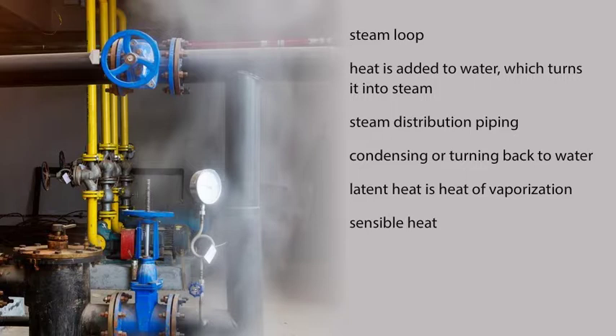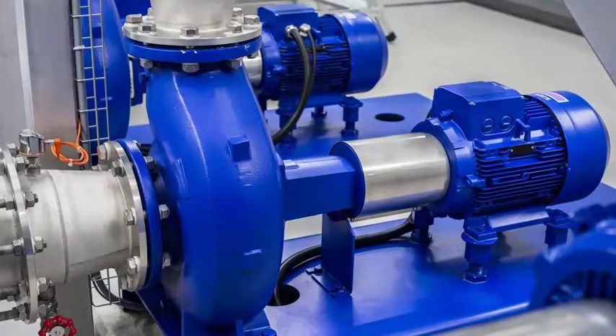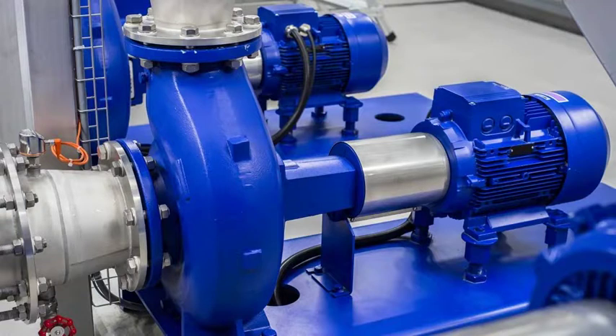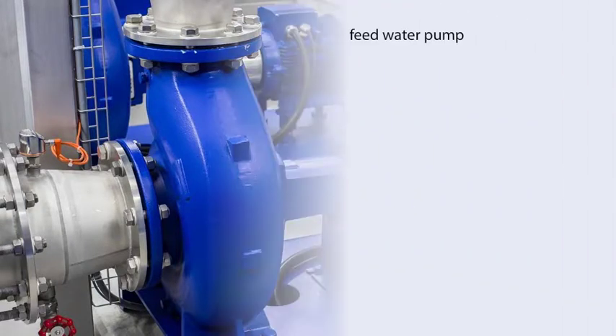When steam gives up its latent energy, it condenses and turns back into water called condensate. The condensate is returned back to a holding tank or a deaerator, where it is processed and conditioned for reuse. At this point, the condensate water's pressure is increased substantially by a feed water pump and returned to the boiler to be heated and converted again to steam.